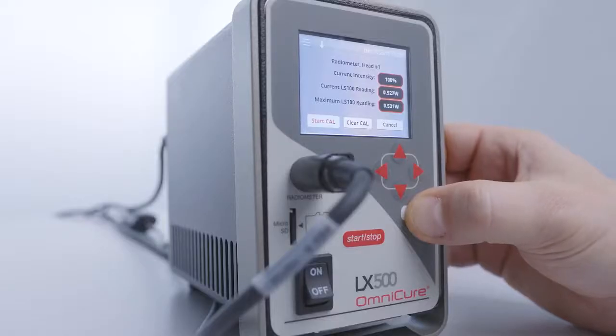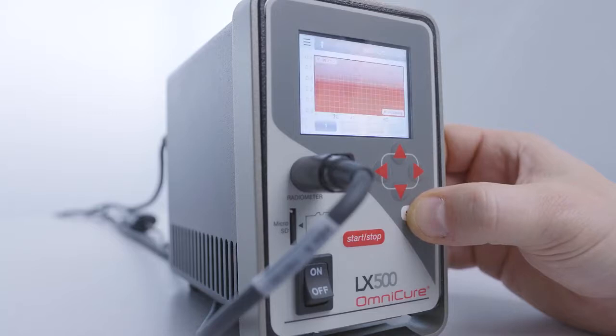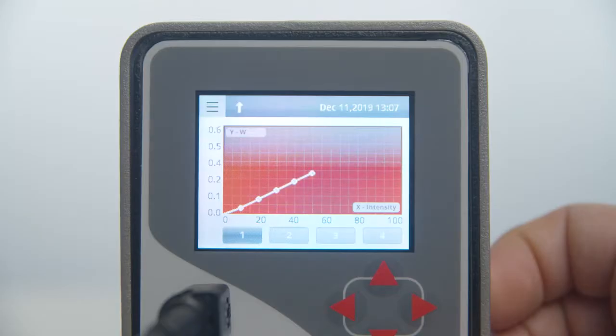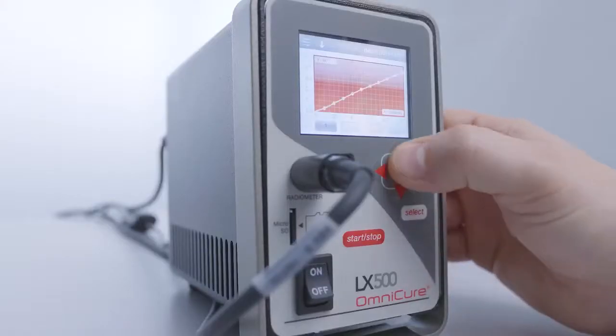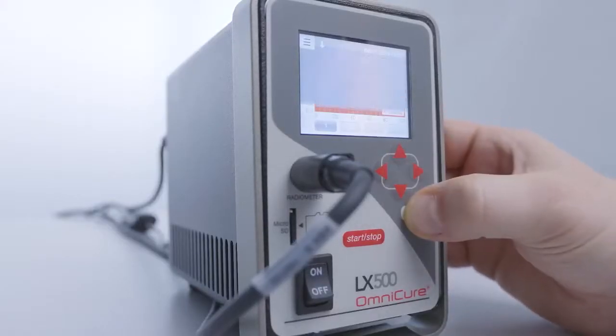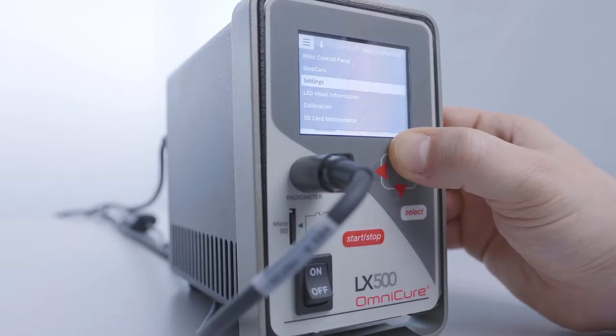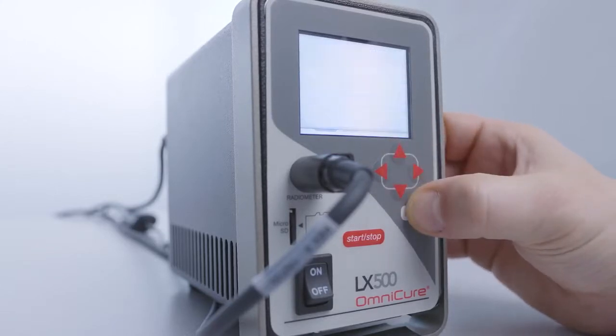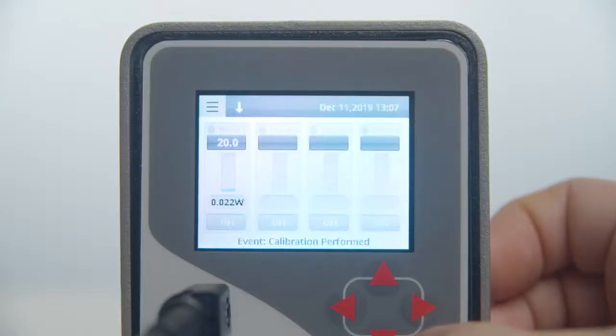When the maximum value has been found and while the LED head is still turned on, the calibration can begin by pressing Select. Once the calibration is complete, it will remain in the system for up to 100 hours, and optical power will be displayed in watts on the main screen. If the LED head is disconnected, the calibration will clear automatically. The calibration can also be manually cleared. Repeat all the previous steps for any additional LED heads connected to the LX500 controller.